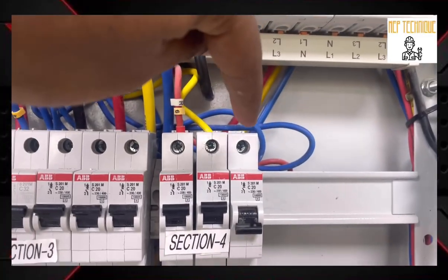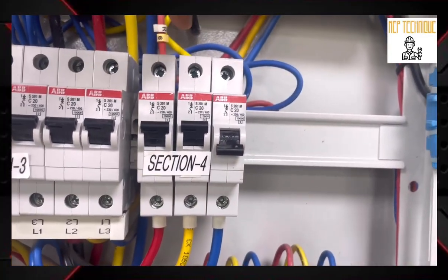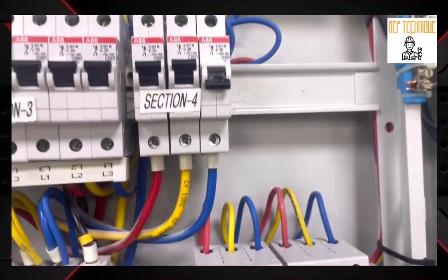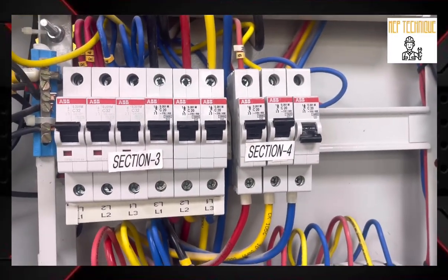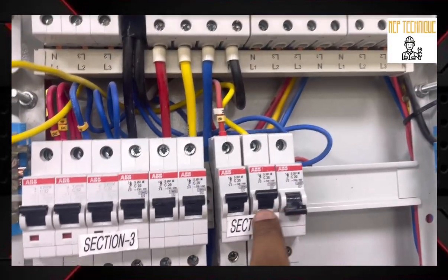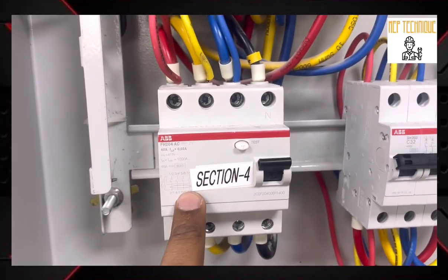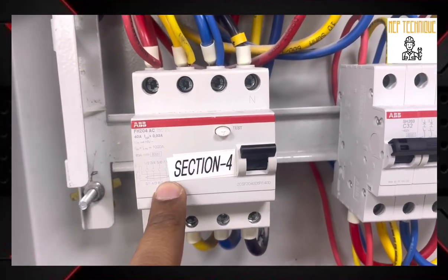There is no load connected with B6. Then R6 and Y6. The question is why the MCB is not getting tripped. As you know, an MCB will only trip if there is an overload or short circuit. If our ELCB is getting tripped, then there is an earth leakage current. So let us measure.